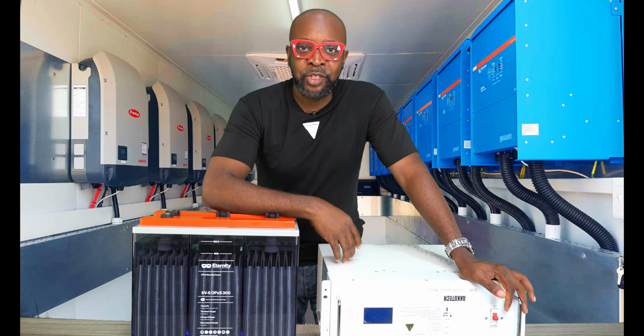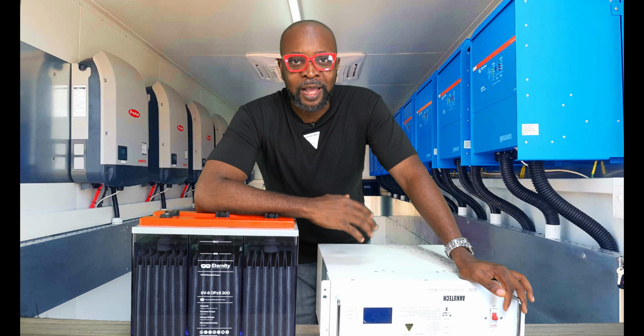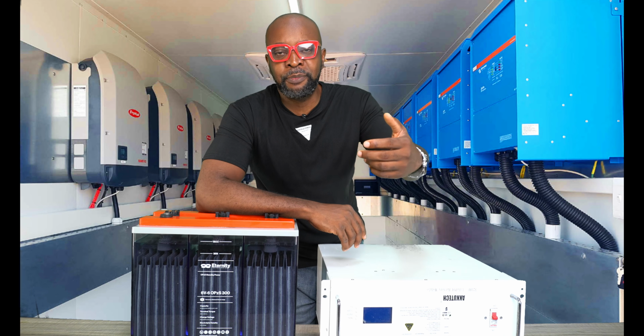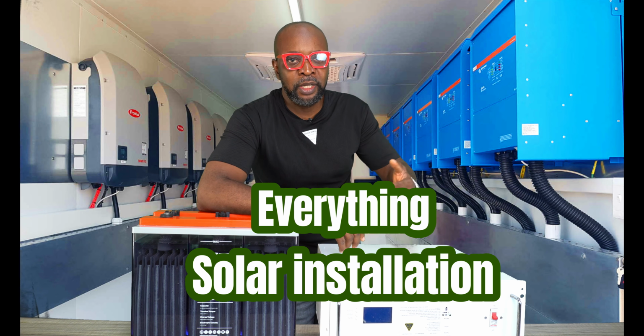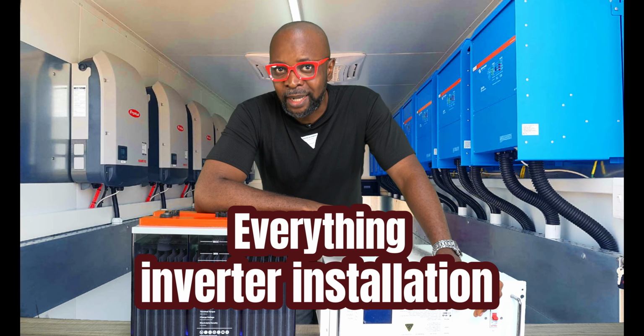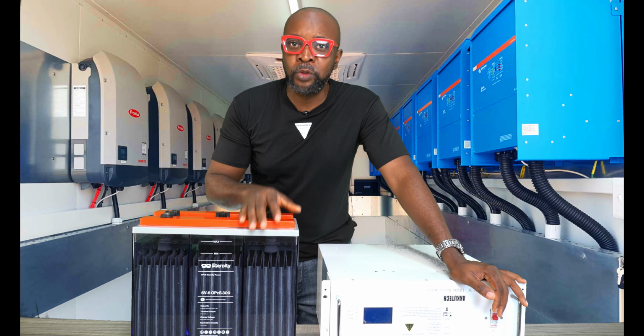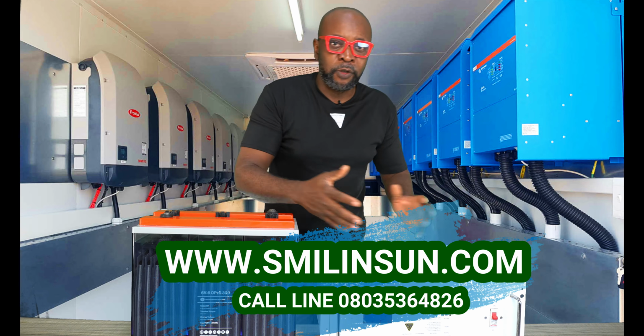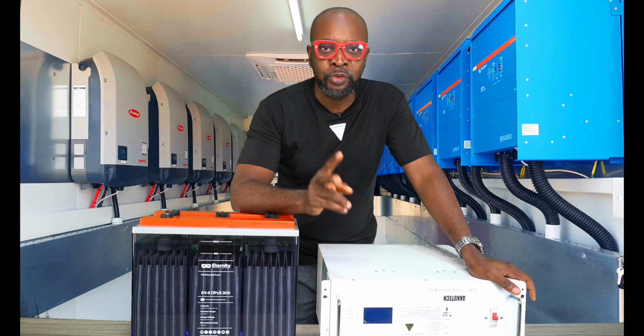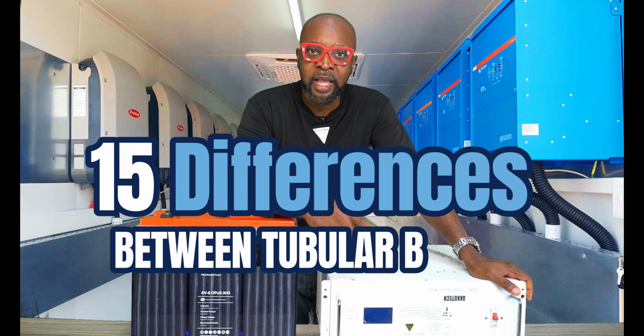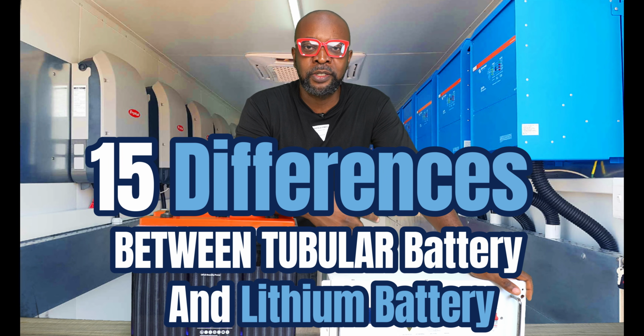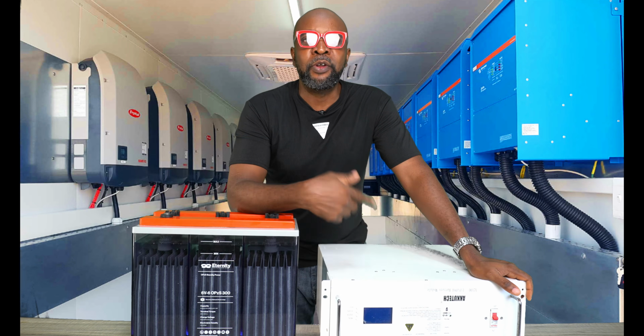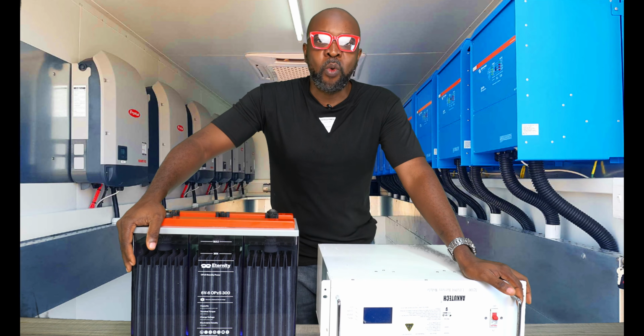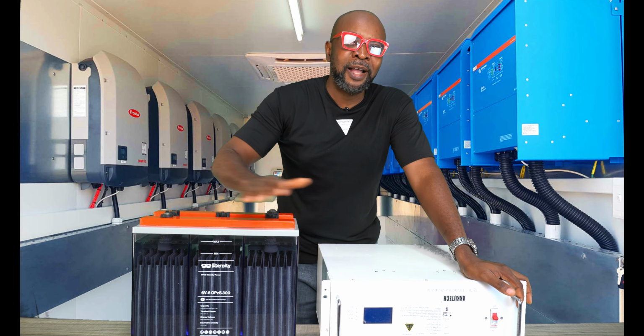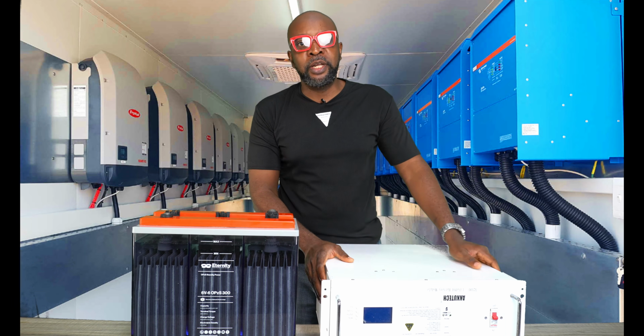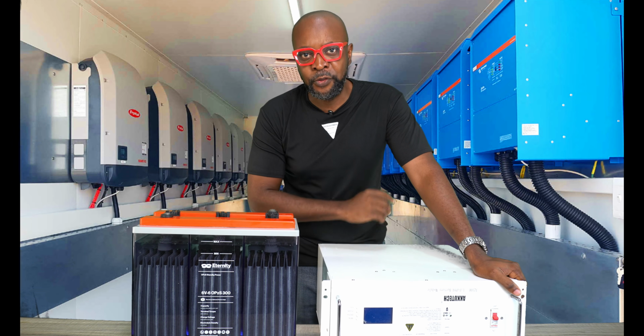You're already aware of the battery charge cycles. You first of all have the bulk charging, then it goes to absorption, and then it comes back to floating, and periodically you go to equalization. So for the tubular battery, it goes through the 4 battery charge cycles. But the lithium battery only goes through 2 cycles of charging, which is bulk charging and floating charging. Once the set voltage is achieved through bulk charging, it reverts back to float charging. So whilst the tubular battery will go through the entire 4 charge cycles, you only need 2 battery charge cycles for the lithium battery.